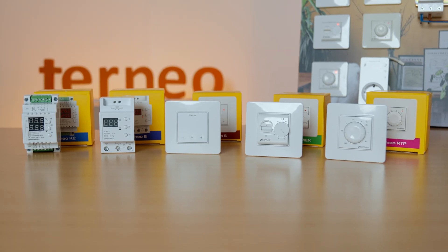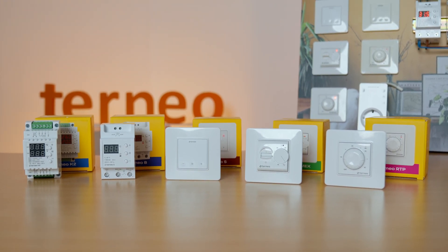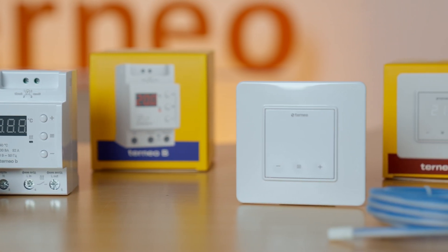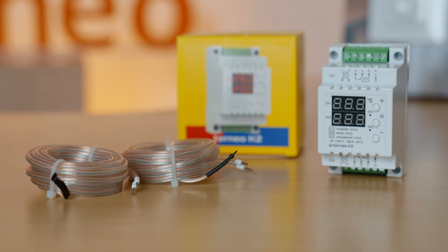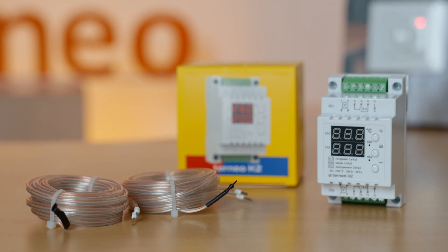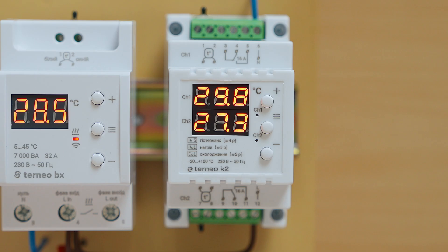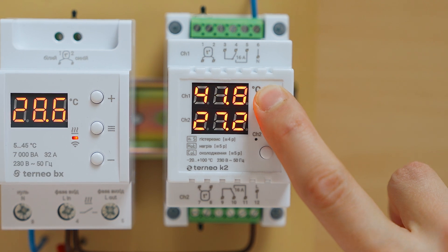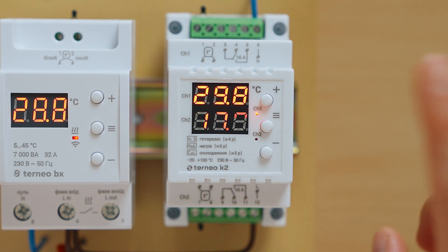Moving on to thermostats that maintain a constant set temperature, we have terneo S and terneo B. These look identical to the terneo SX and BX versions, but without Wi-Fi features and without a schedule. We also have the terneo K2 thermostat, which can manage two separate underfloor heating systems, each one up to 3 kW – like two thermostats in one with two separate sensors. It has a wide temperature range, from minus 20 to plus 100 degrees Celsius, making it a good choice for more niche and specific tasks.